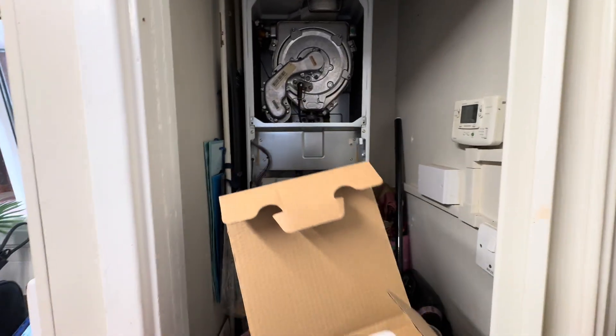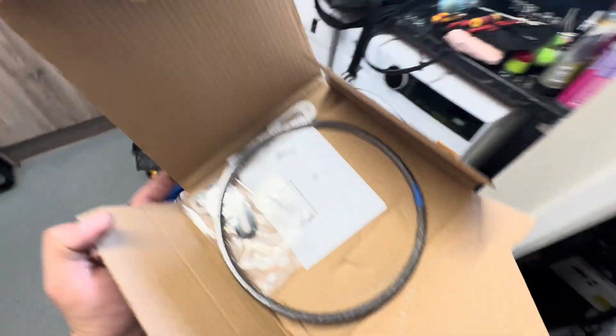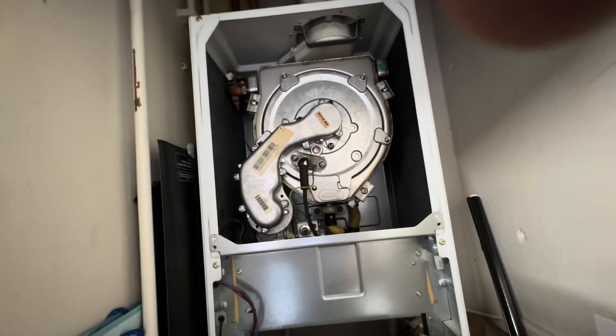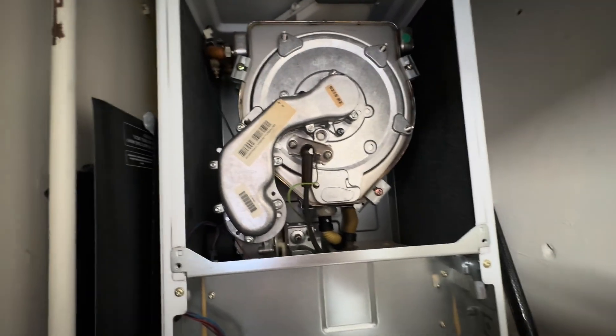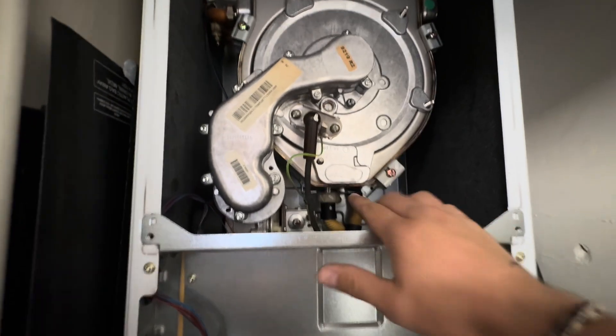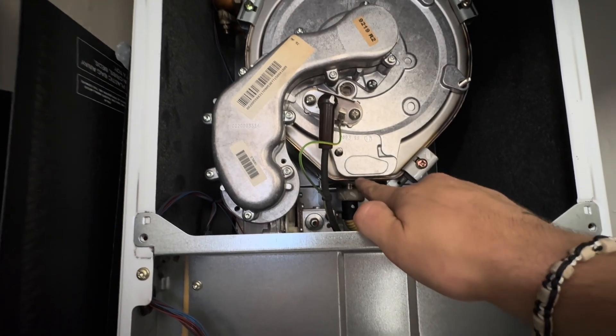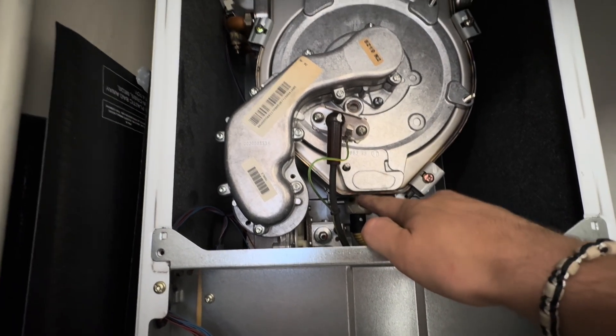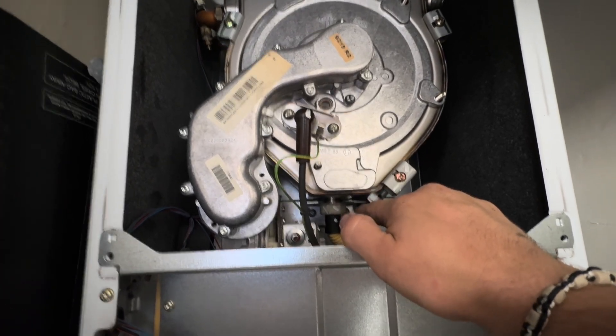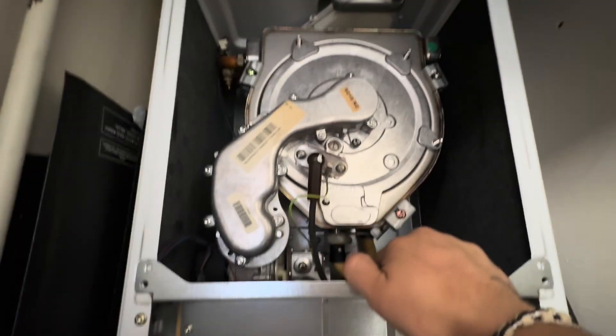Here we go with a Vaillant Ecotec Plus G10 seal replacement. I started the video a little bit late as I forgot I should be recording. What I've already done is take off the case — you can usually see some kind of crust. You can also put your analyzer here; if you get some readings it usually indicates that the G10 seal needs replacing. I usually replace these every five years anyway as standard.